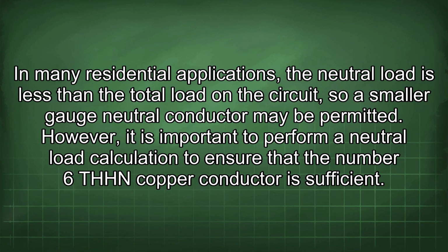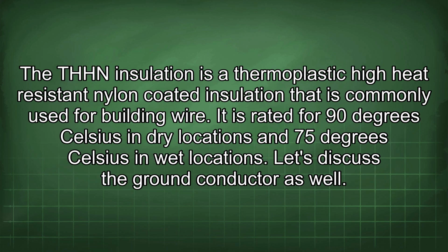However, it is important to perform a neutral load calculation to ensure that the number 6 THHN copper conductor is sufficient. The THHN insulation is a thermoplastic high heat resistant nylon coated insulation that is commonly used for building wire. It is rated for 90 degrees Celsius in dry locations and 75 degrees Celsius in wet locations.